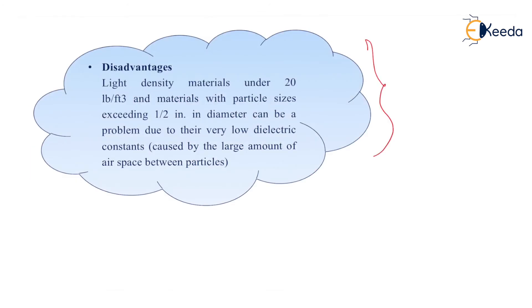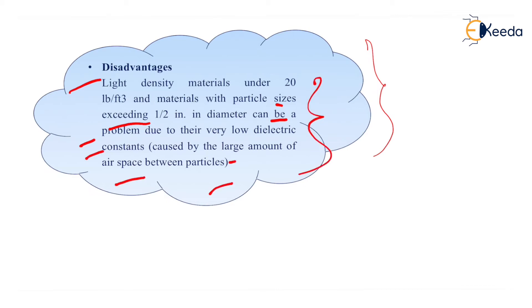There are also some disadvantages of capacitive level measurement. Light density materials under 20 lb per cubic foot and materials with particle size exceeding half an inch in diameter can be problematic due to their low dielectric constant, caused by the large amount of air space between the particles. For these conditions, accurate results cannot be obtained.